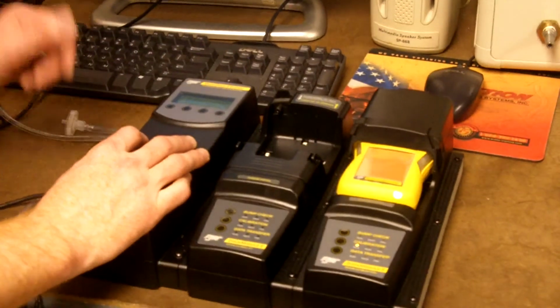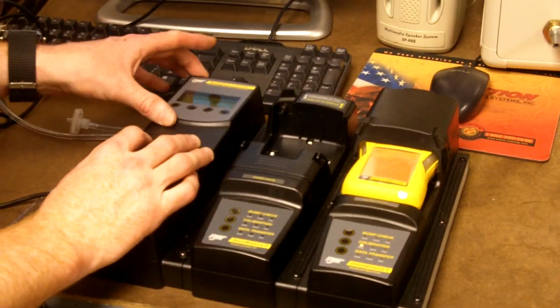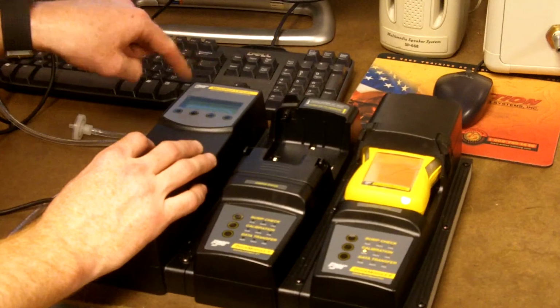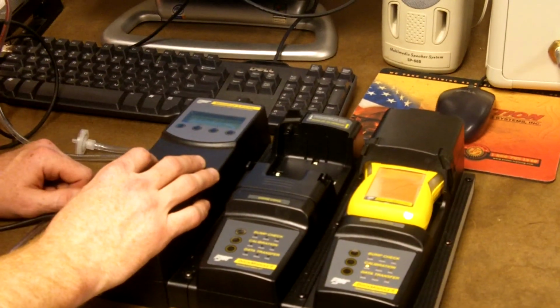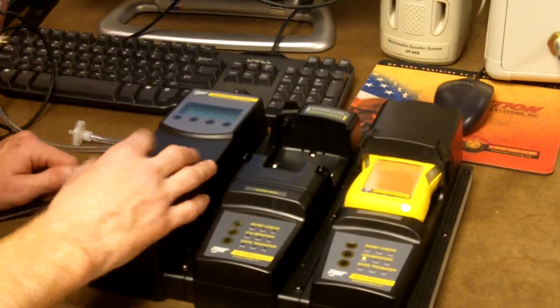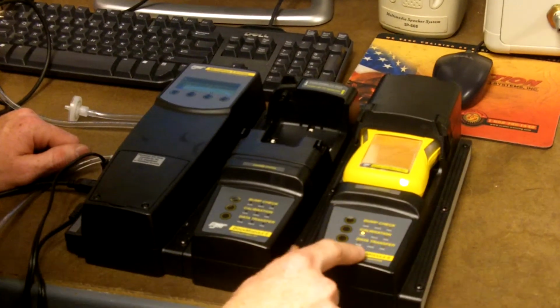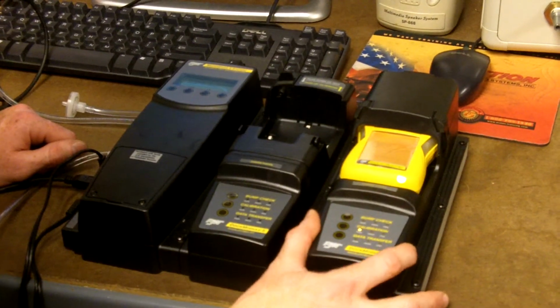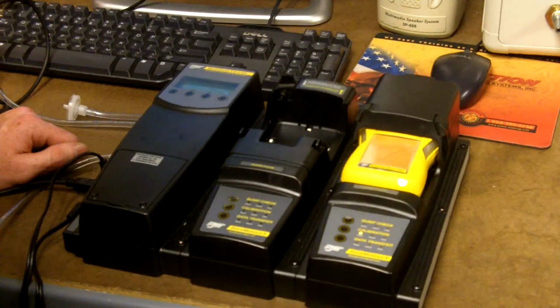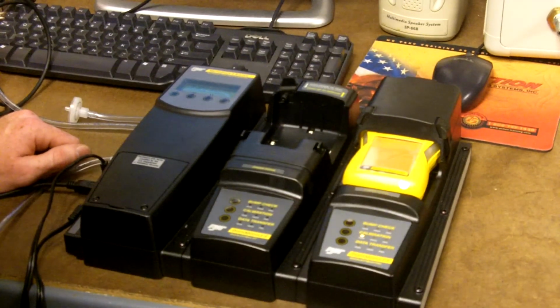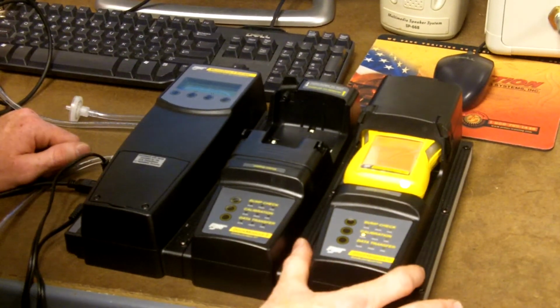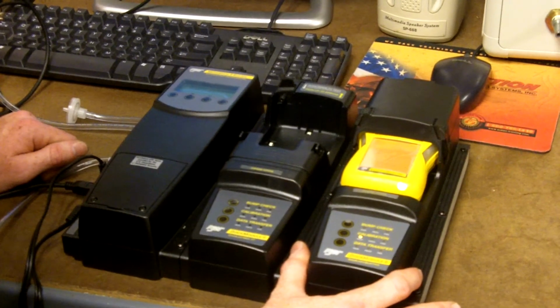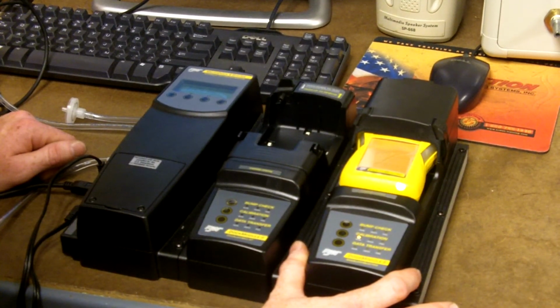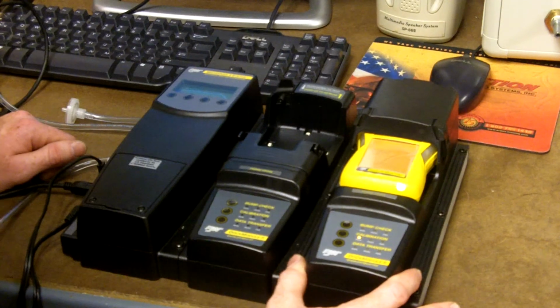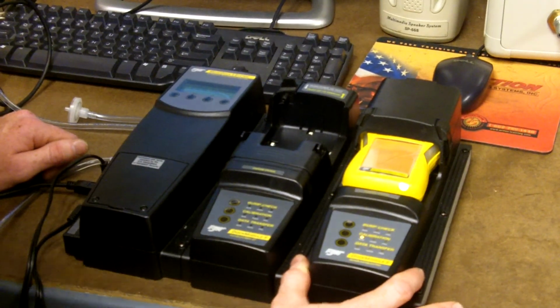Now back to our calibration that's going on. In the meantime, it's still calibrating. When it's done, it's going to have little checks next to each one, if it's good or not. And also on the docking station under calibration, it should have a green light on the pass if it's passed, or if it's failed, to have the red light. If it's failed, tag it out of service and notify me, and I'll be able to send it off or repair it. So, and that is all.